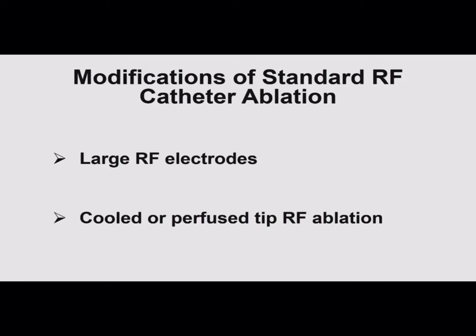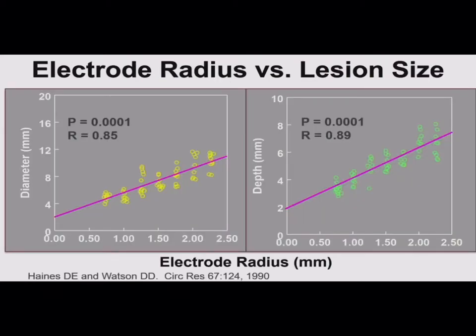Because of some of these limitations, larger RF electrodes were developed. Early work from David Haines showed that if you make the zone of resistive heating bigger and then have conductive heating from there, you're going to make your whole lesion larger. The key point is that presumes you're heating the tissue-electrode interface to the same temperature. With a larger electrode, you may actually have to deliver more power to get to that same temperature, and then you'll get a larger lesion with a larger electrode radius.